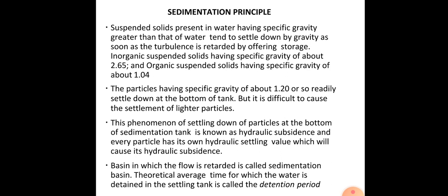And the phenomenon of the settling down of the particles at the bottom of the tank, like I told you, the particles under the force of gravity will settle towards the bottom of the tank. This phenomenon is called hydraulic subsidence, and each particle will have its own hydraulic settling value that causes the hydraulic subsidence. In the tank or basin the flow is retarded, since water flows from one treatment unit to the other. In the sedimentation tank, the flow of water will be retarded, and the average time for which the water will be detained in the tank, we call the detention period.